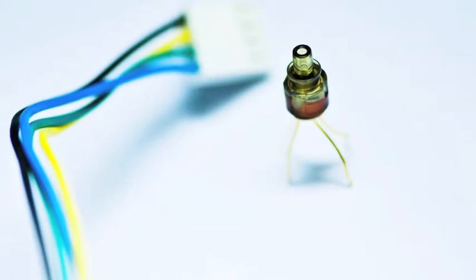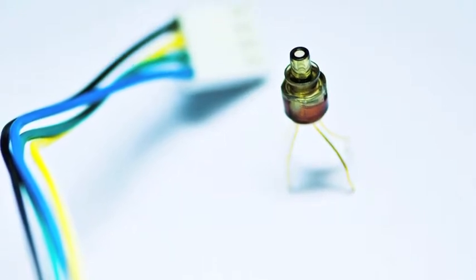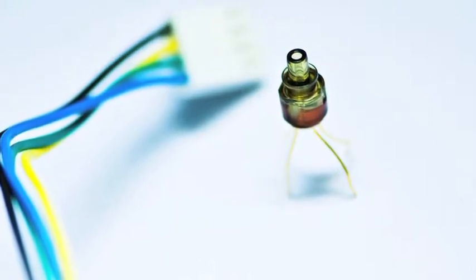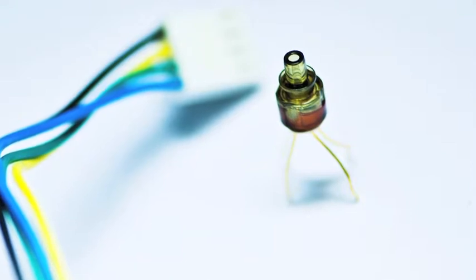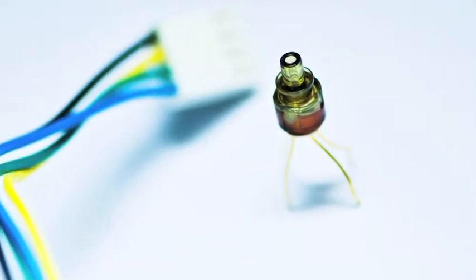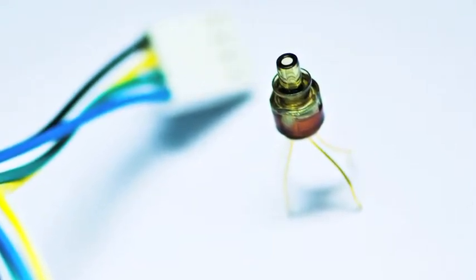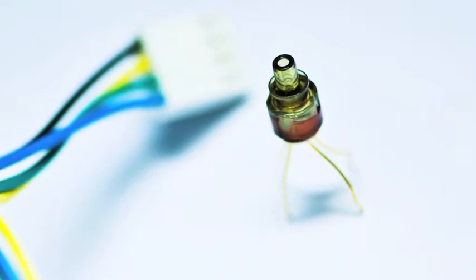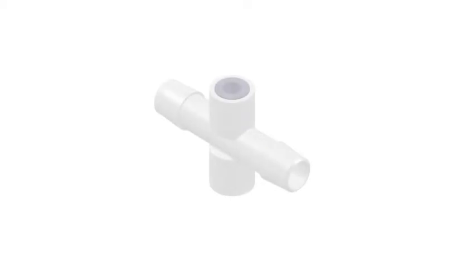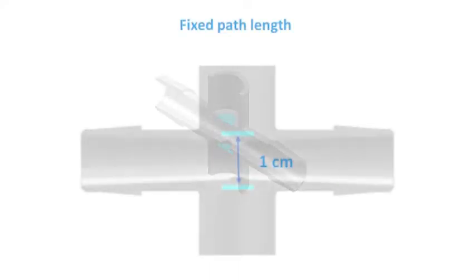The photometer has a single wavelength light source that is generated by a light-emitting diode, most often referred to as an LED. An LED generates minimum heat as compared to a lamp and has a lifetime of greater than 5 years. The lenses embedded on the wall of the flow cell are made of fused silica glass, which is ultra-pure glass with no impurities to absorb the light which would interfere with measurements.